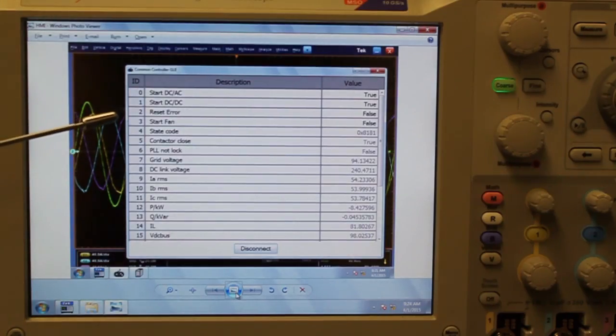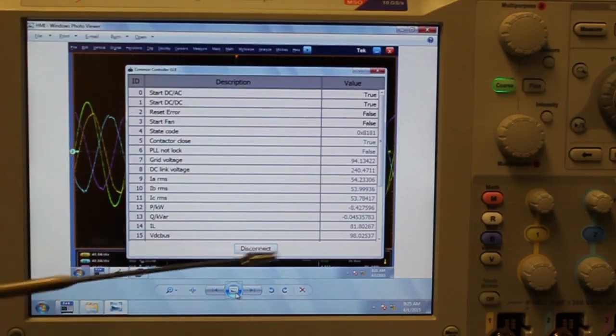This screen shows the human-machine interface, which is used to control the system and display the system variables. The start command can be set to the two stages separately, and the system running status, like PLL and contactor status, are indicated in this human-machine interface. The key variables of the converter, like the grid voltage, grid current, DC-link voltage, active and reactive power, and DC set voltage and current, are also displayed by this human-machine interface.